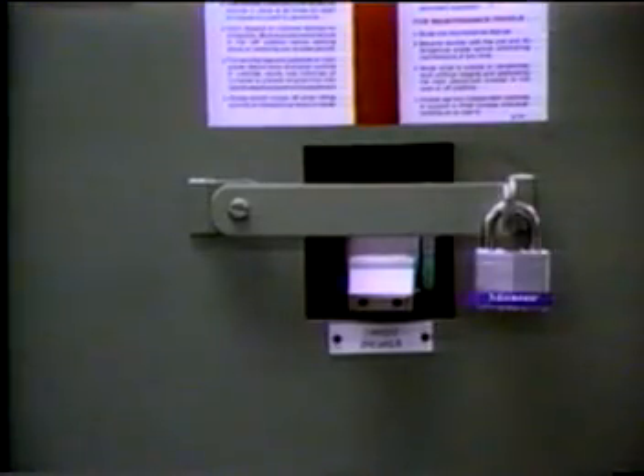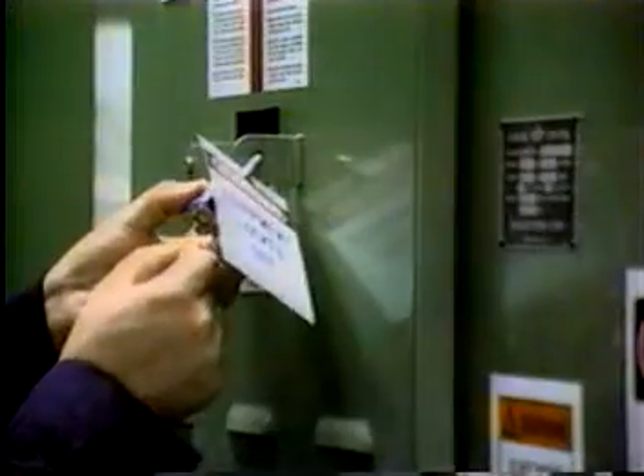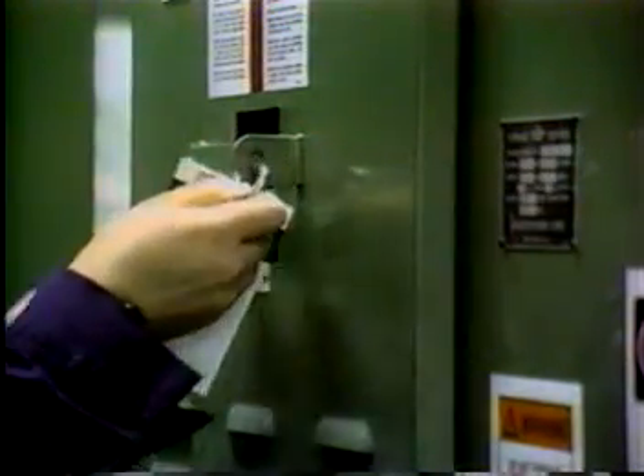With this system, the individual performing the service work uses a lock to secure the circuit breaker in the off position. He or she then keeps the only key until the service work is complete and the equipment is ready to be restored to operation. At that time, the same individual who put on the lock removes it, allowing the breaker to be closed and power to be turned on.